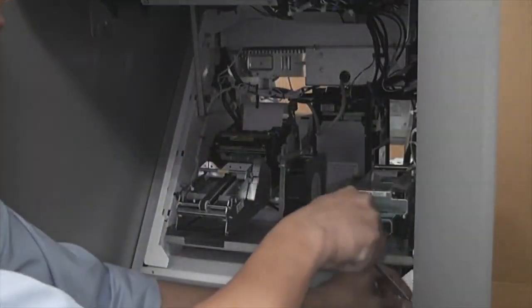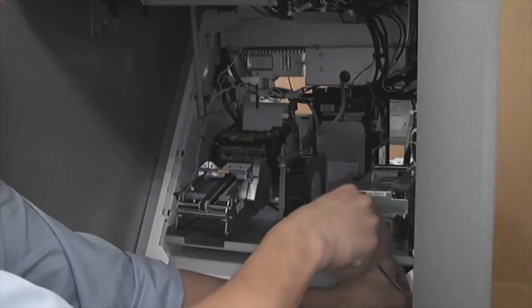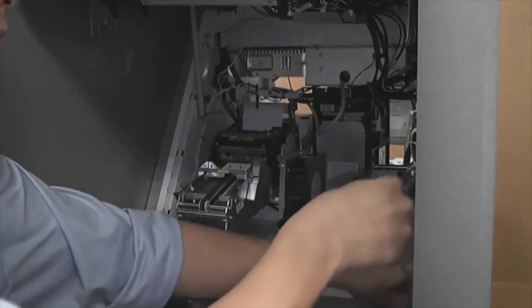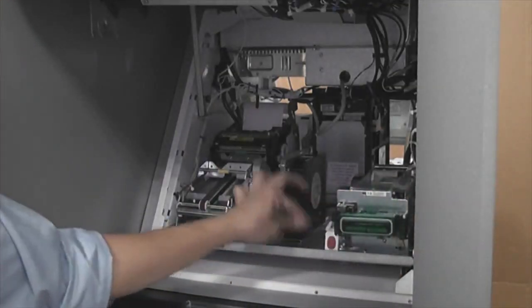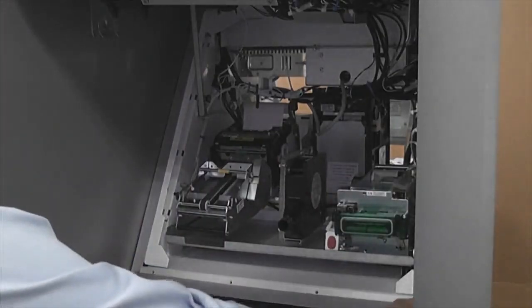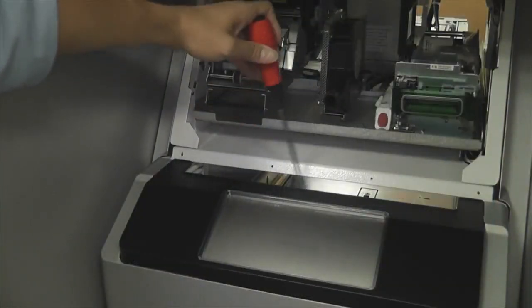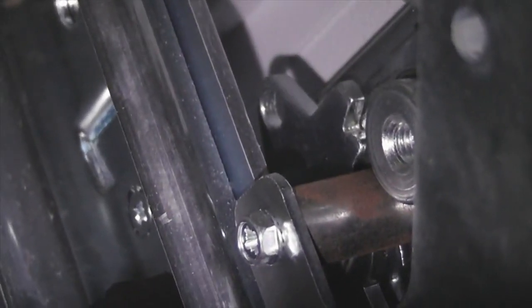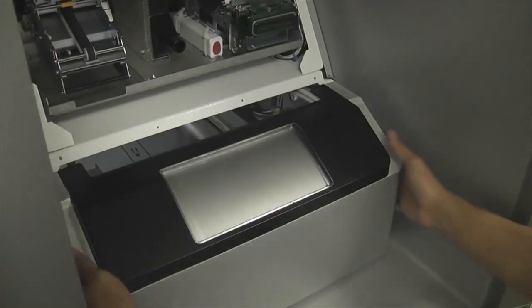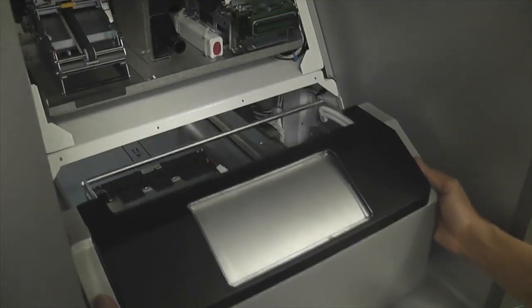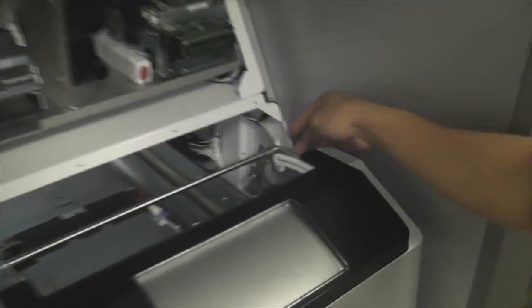Remove the shutter cover screws. Remove the cover. Unlock the shutter assembly latch on each side. After disconnecting the white signal and power connector, the shutter assembly can be removed.